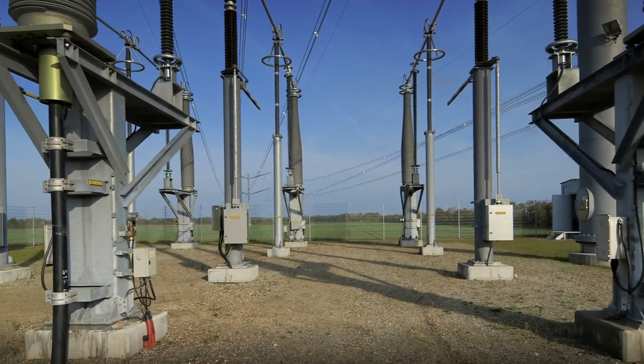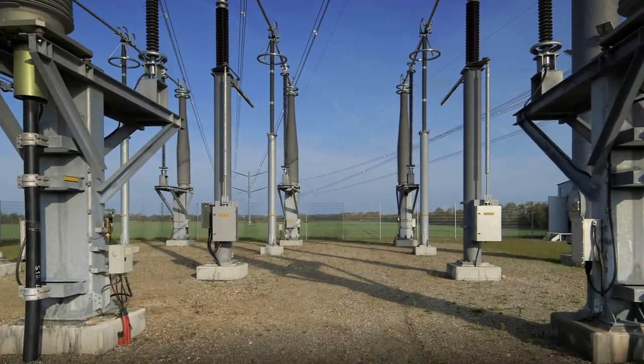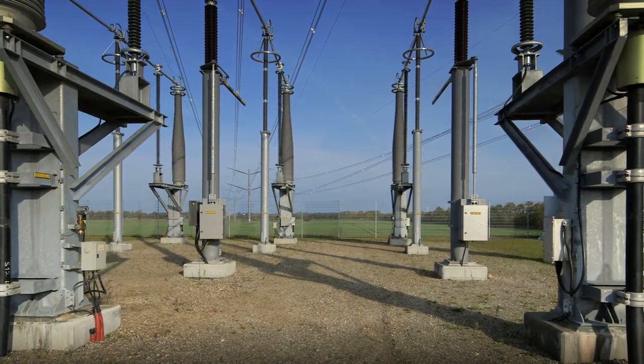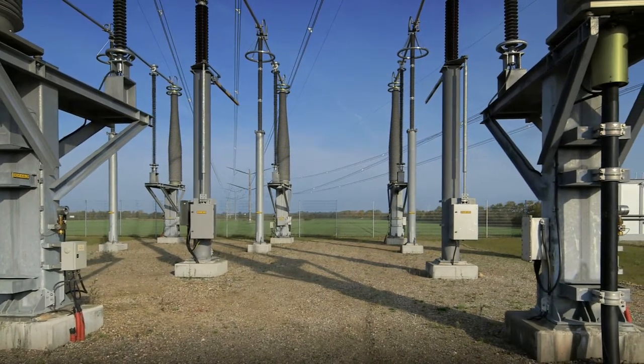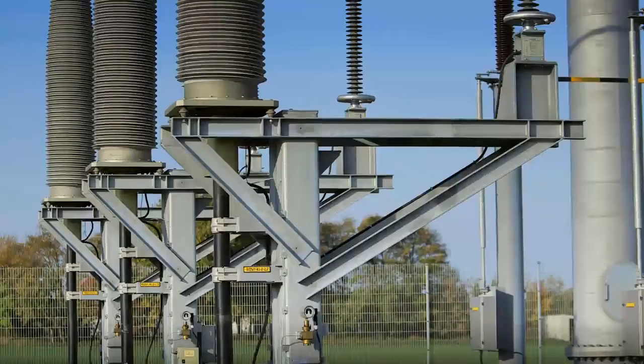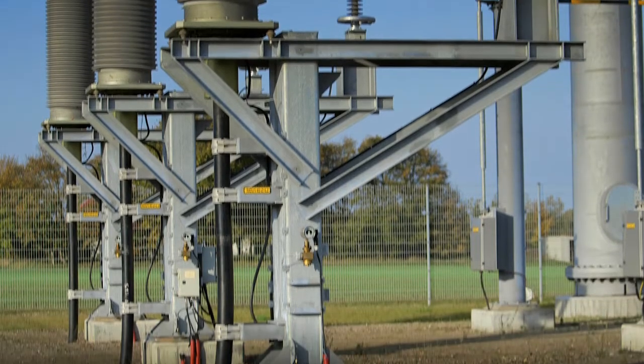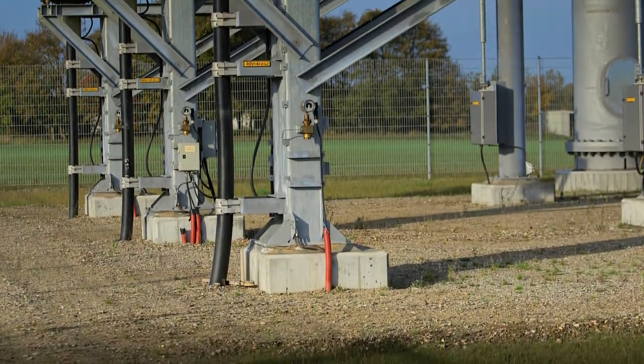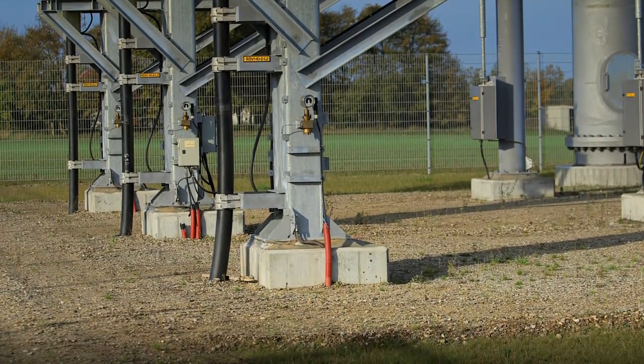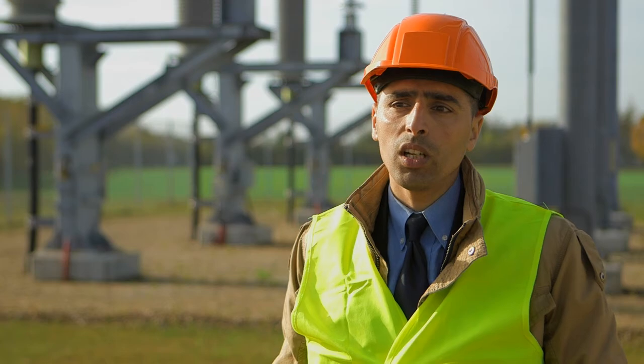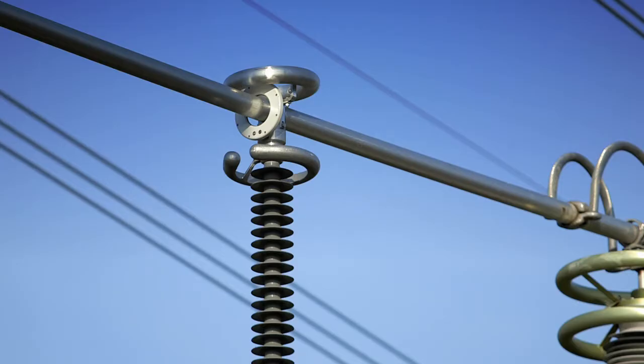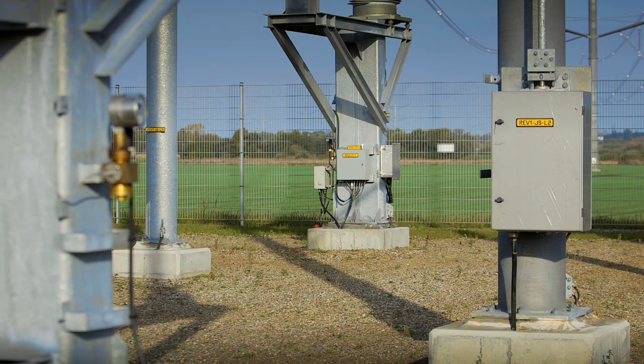The main characteristic of the equipment, I would say, is obviously the weight. Typically, in our example, we can install the CT and the terminal bushing in the same structure thanks to the light weight. The second one should be the non-saturation of the sensor. In the white donut on the top of the CT, we have an optical fiber. There is no magnetic core and no saturation. It makes it easier for the engineering to define the CT.